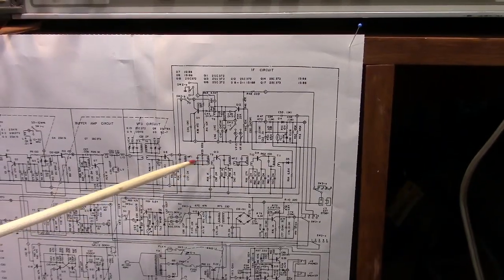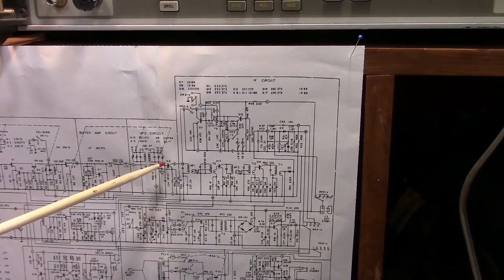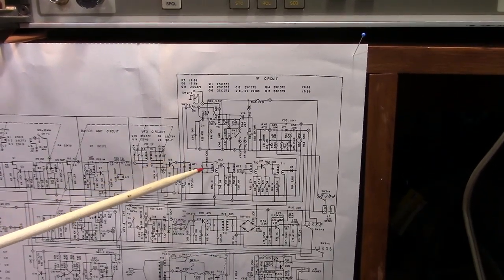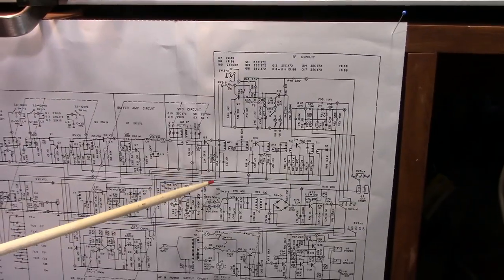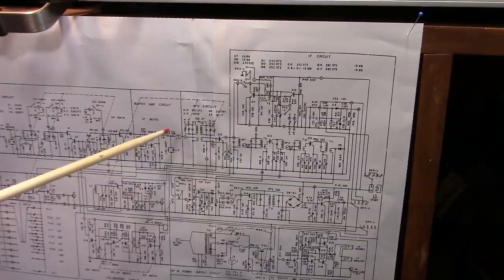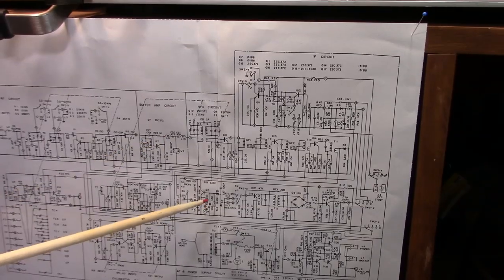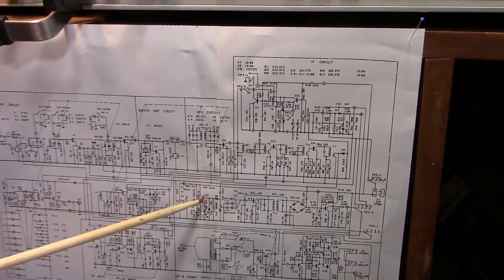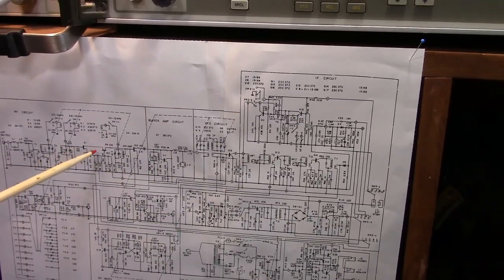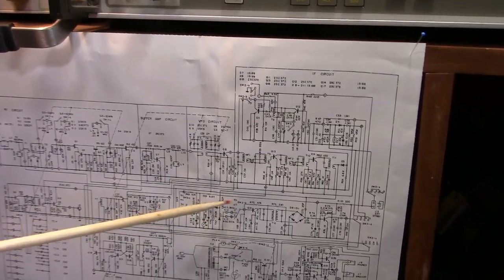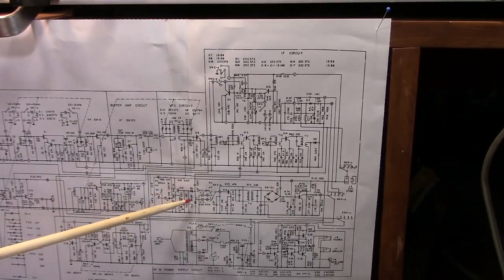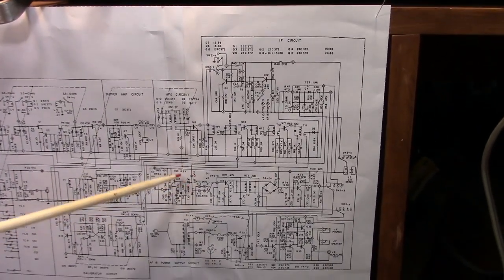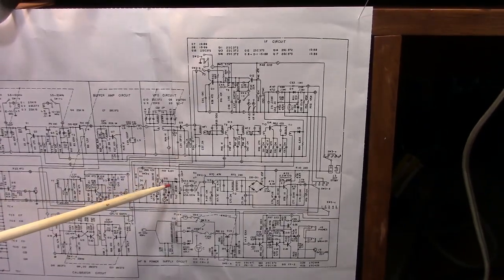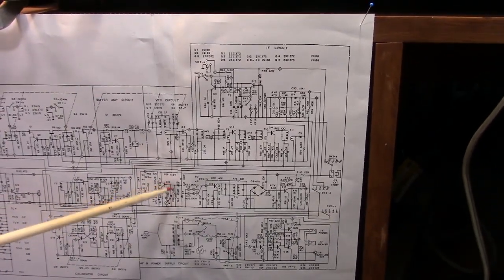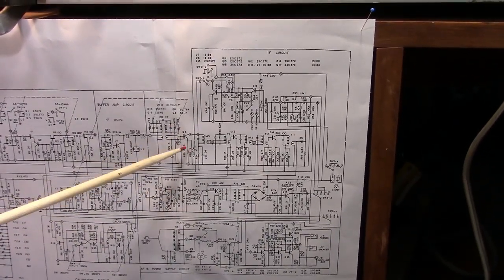One thing you want to keep in mind through this procedure is keep your levels low enough so you don't activate the AGC system down here. If you start bringing your levels too high, the AGC circuit is going to start biasing down the level and you'll get erroneous readings. So that's one of the things you want to do here. In the past, a lot of times they would have you actually disable the AGC, but in this case I'm going to keep the levels low enough. It shouldn't be a problem.